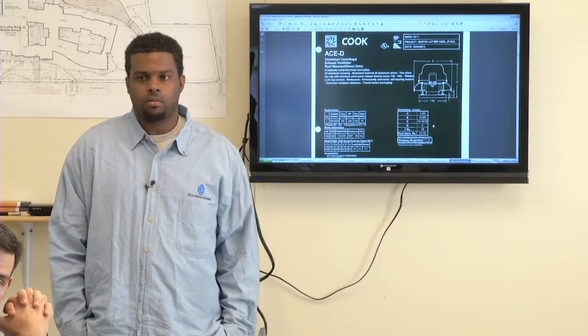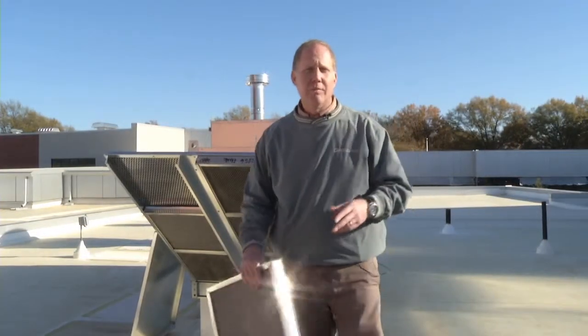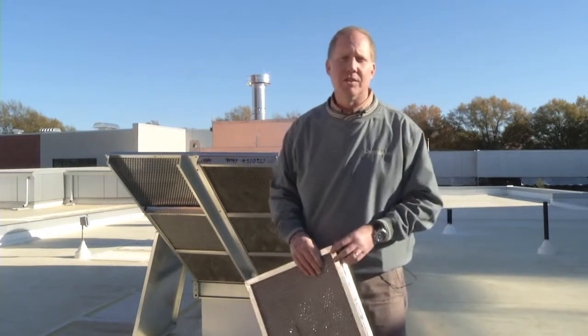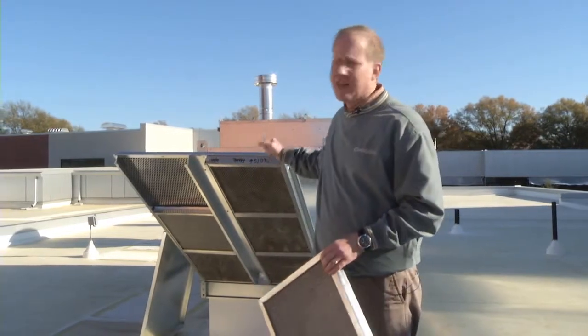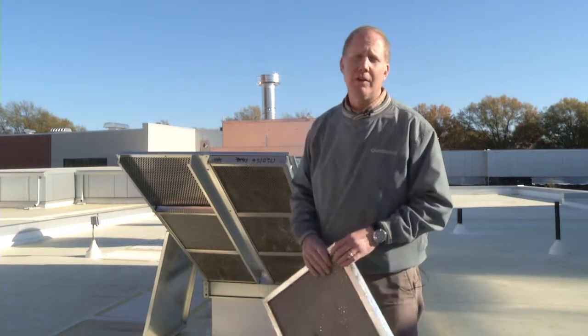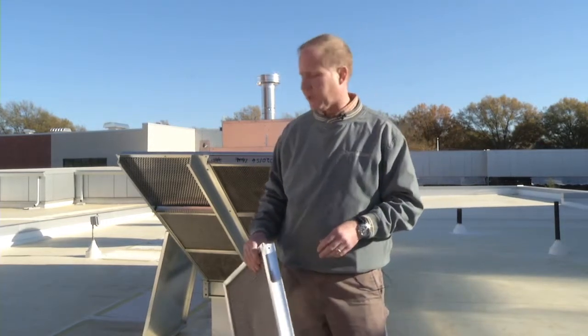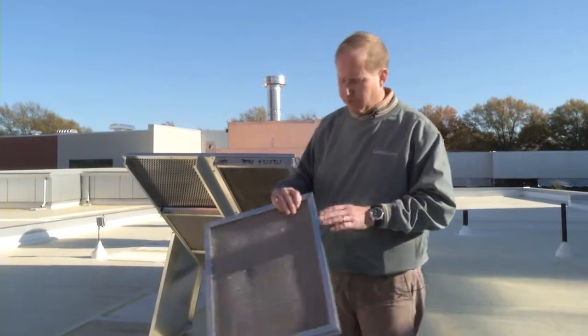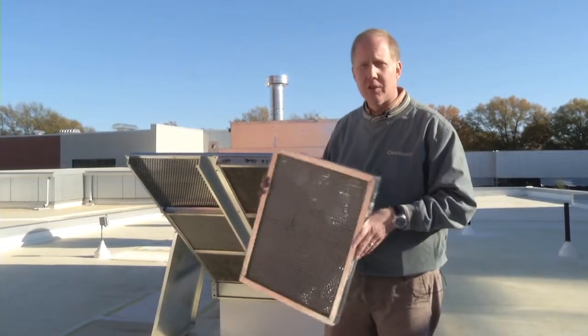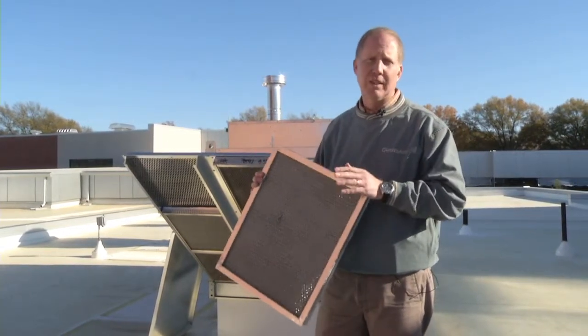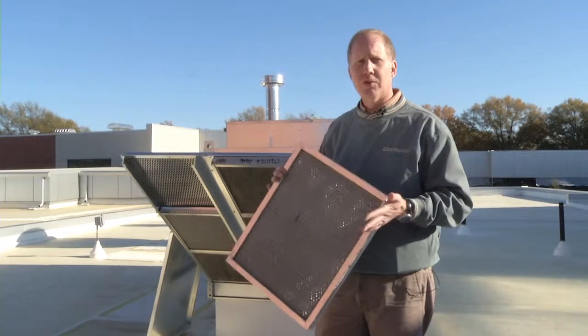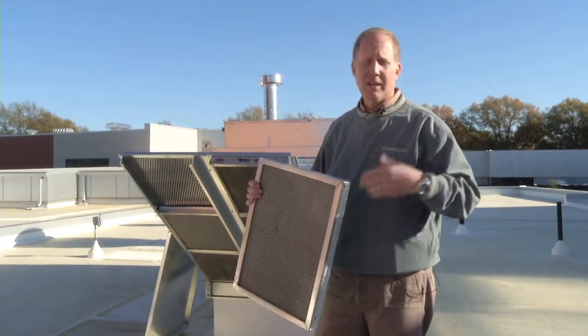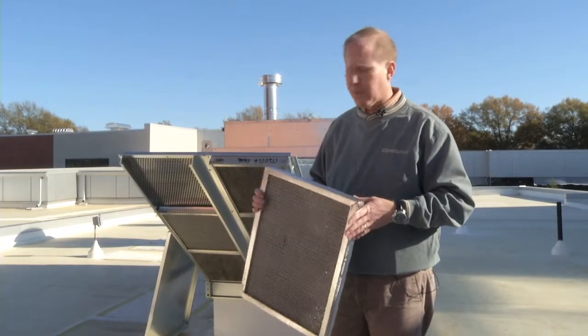Okay, good afternoon. My name is Trey Harmon. I'm with CaptiveAire Systems. We supplied the indirect fired heated makeup air unit for the hood system that was shown previously. First things first is the filtration for these units. You're going to want to check these two to three times a year. We tell most schools just to do it at the beginning and end of each semester.